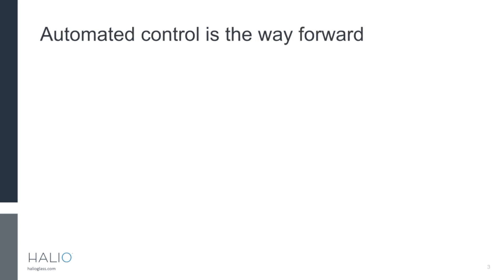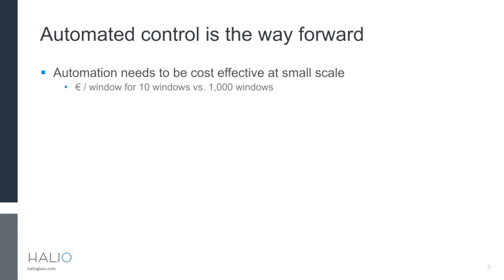So the answer is automated controls for our shading systems. That's becoming much more common on large, high-spec buildings, but smaller buildings and residences are still left out of automation. Part of the reason is that automation needs to be cost-effective at that scale. System costs — like centralized control hardware, commissioning, sensors on the roof — might be absorbed easily by a building with 1,000 windows, but a building with 10 windows can't absorb those costs.